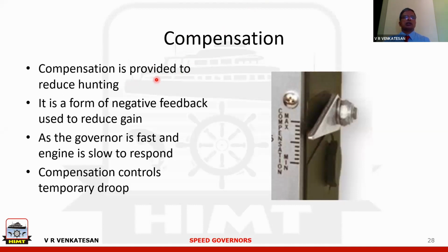In any control system, it is because the gain of the controller is high and the system is slow to respond. Often that will be the reason. Between the engine and the governor, the governor is fast to react, but the engine will be much slower because of the inertia. So what is going to happen is, if the load on the engine increases and because of that the speed comes down, fuel is increased. The engine will not pick up speed immediately.